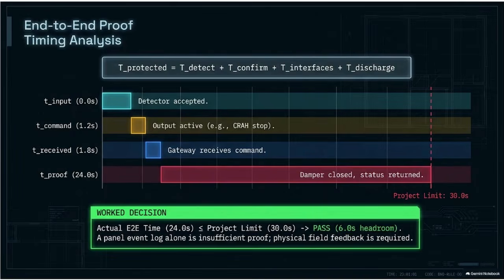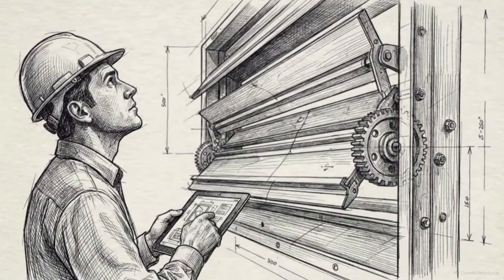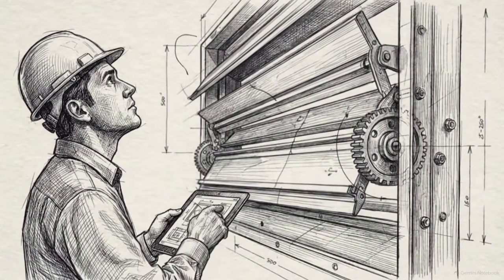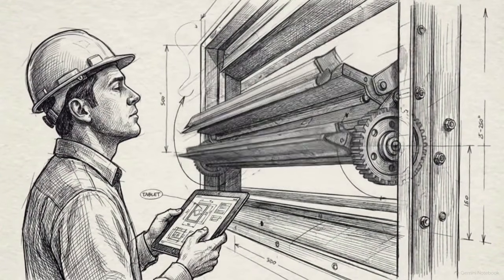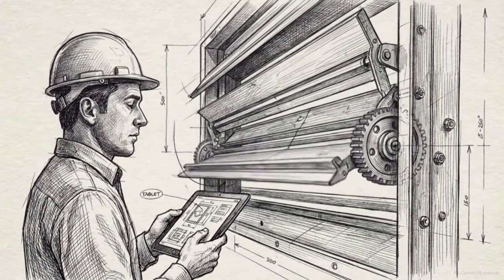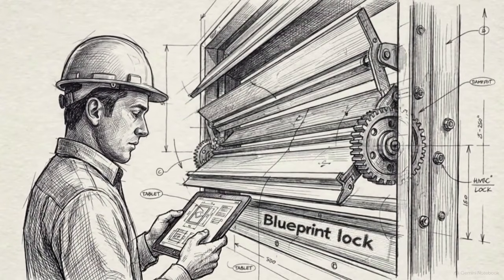This timing analysis chart shows the equation for end-to-end proof. Total protected time equals detection, confirmation, routing, and discharge. Here, command issues at 1.2 seconds, but required field proof, the physical damper closing, takes 24 seconds. It passes, falling under the 30-second limit. A digital event log exported from a fire panel is insufficient proof of protection. Only validated physical field feedback proves the contract has been successfully executed.